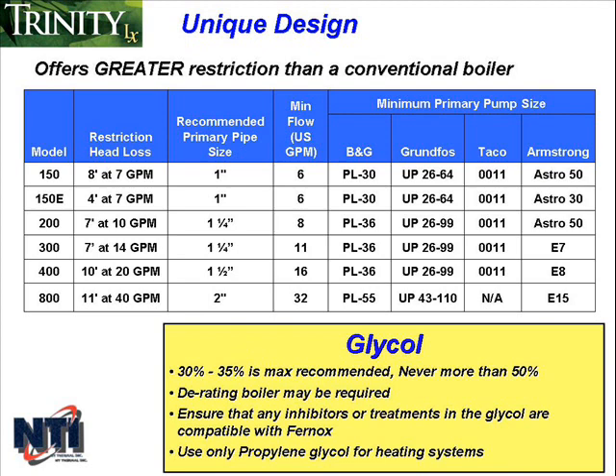Due to the design of the LX, it's more restrictive than conventional boilers, and there can be a tendency to underestimate the size of the pump required on the primary loop and for domestic hot water. We lay out in the manual the minimum pump sizes required for each model. It indicates a specific pump across 4 different pump manufacturers for each LX model. These are the minimum size pumps that should be used for each the primary pump and the domestic hot water pump when using the boiler with an indirect. The chart also shows the minimum flow rate for the primary loop, the restriction head loss for the boiler itself, and the recommended size pipe to be used for the primary loop.